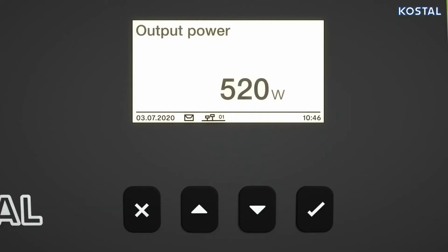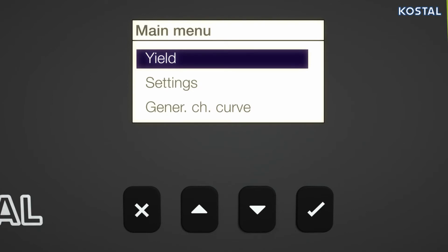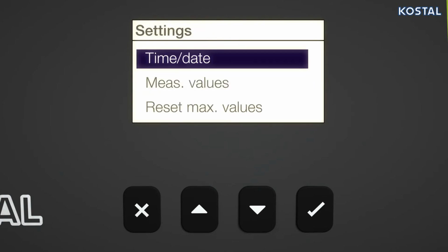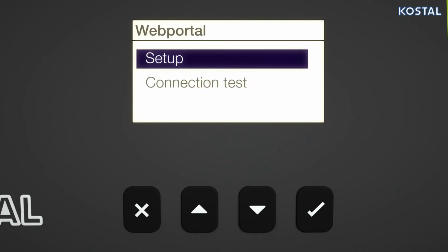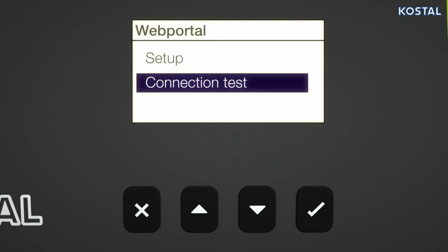If you want to display the yield, consumption, and battery data in one system, the transmission of these data to the solar portal must be activated in the PIKO MP Plus and also in the KOSTAL Smart Energy Meter. Add both devices to the same plant in the solar portal. In the main menu of the PIKO MP Plus, use the arrow key to go to Settings. Then Network and finally Web Portal. Activate Setup to confirm data transmission. You can now use the Connection Test menu item to check communication with the solar portal.